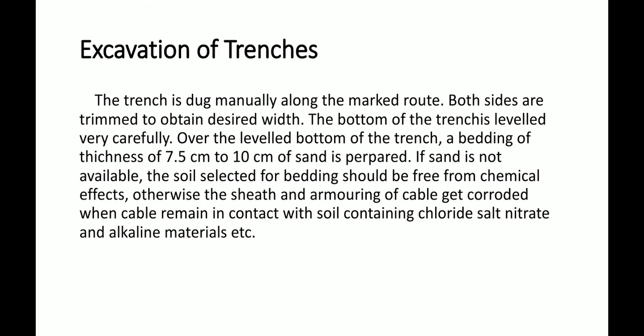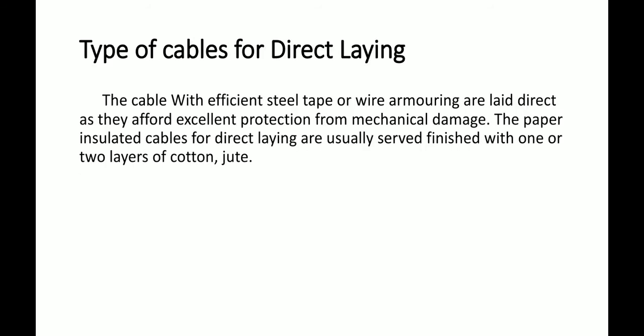When the soil contains chloride salt, nitrate, alkaline material, and similar chemical content, the armoring of the cable will be affected. Cables with effective steel taping or wire armoring are laid directly as they afford excellent protection from mechanical damage.